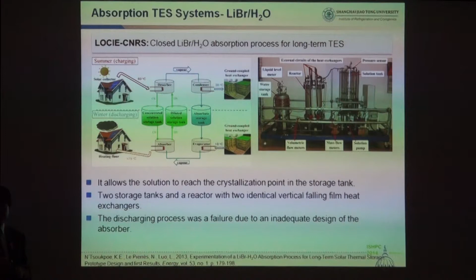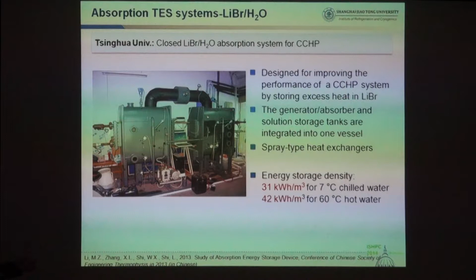Another good example is a successful case at Tsinghua University: a CCHP, combined cooling, heating and power system, where heat from the engine is recovered for thermal storage using lithium bromide water. There's one tank with lithium bromide solution and another tank with water. For chilled water output for energy storage, they get nearly 31 kWh per cubic meter. For 60 degree hot water output using absorption heat release, that's about 42 kWh per cubic meter. This system is already integrated into the CCHP system with flexibility for thermal energy storage.